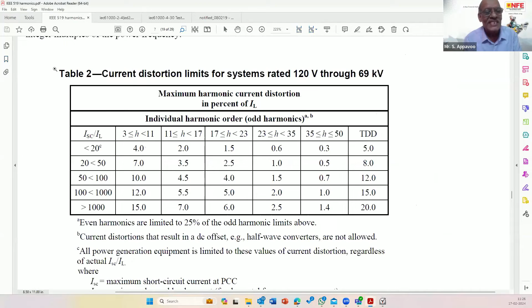If it is more than 20 and up to 50, you can pollute more because the grid is strong — it can go up to 8%. So it goes on. In short, ISC by IL is the factor that poses a threat to the consumer and forms the basis for what he has to do to contain his limits. If there is a strong grid, you can pollute more; if there is a weak grid, you are totally restricted — you can't pollute.